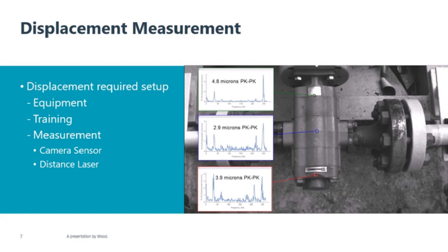Also looking at the frequency graphs, there's a bit of a band there. There's no great peak. You obviously still see the gear meshing frequency, but you also see the motor frequency, you see flow noises as well, and that's okay. That's all quite low, so it's not really vibrating very much.